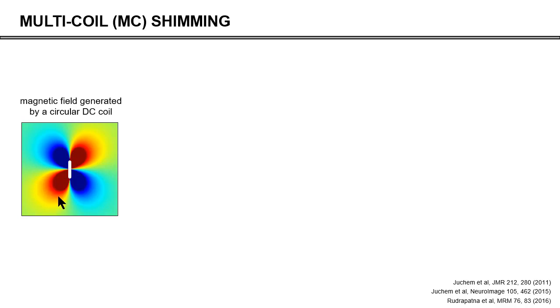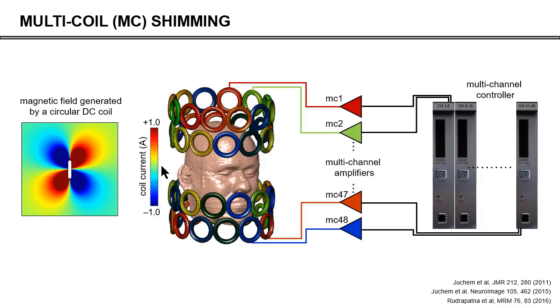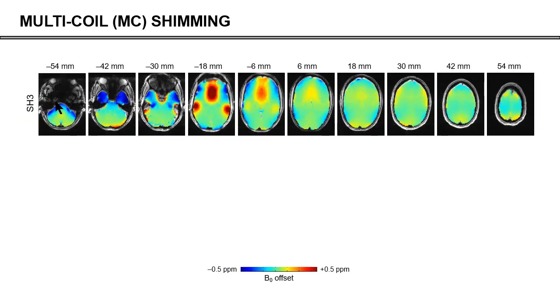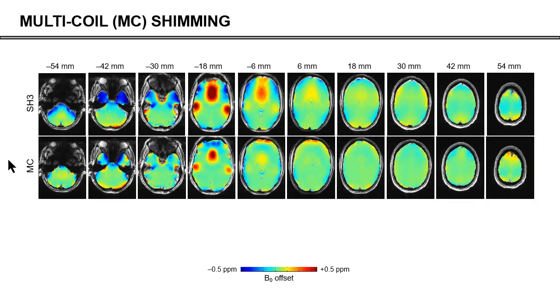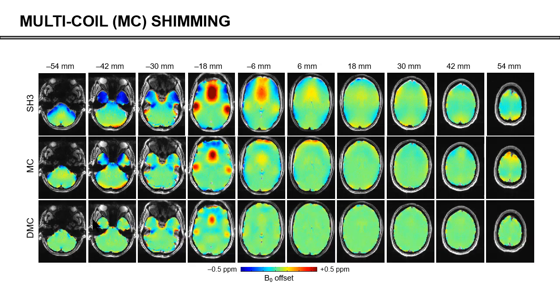Spherical harmonics is just one of an infinite number of functions that you can use. Maybe there is a better set of functions out there, and perhaps functions generated by just little circular coils might be a better choice. We have been pursuing that — we call it multi-coil shimming. If you take a whole bunch of these coils and place them around the human head in four rows of 12, and make sure every little coil has its own individual controller and amplifier and you put the right amount of current in each, then ideally you should get much better homogeneity than with spherical harmonic shimming. This is basically the best you can do with third-order spherical harmonic shims. If you use the multi-coil, things are a lot greener. And if you use a multi-coil in a dynamic fashion, it really starts to become very, very green — not perfect, but very, very good.